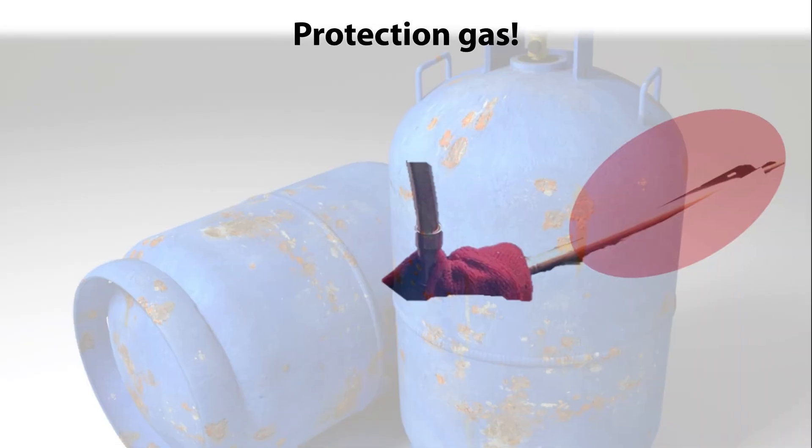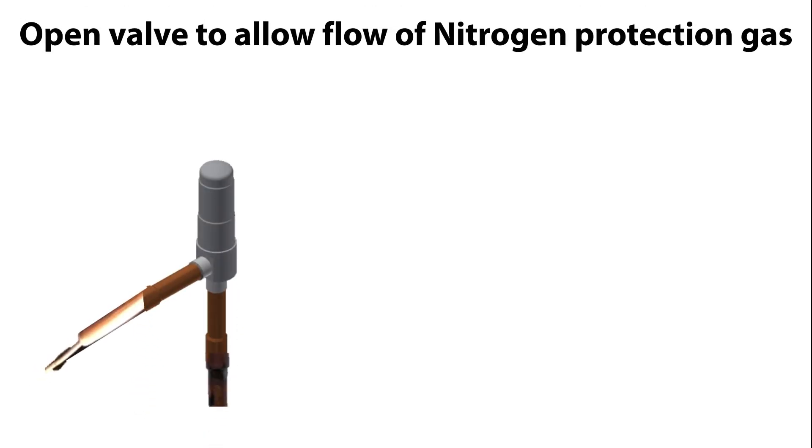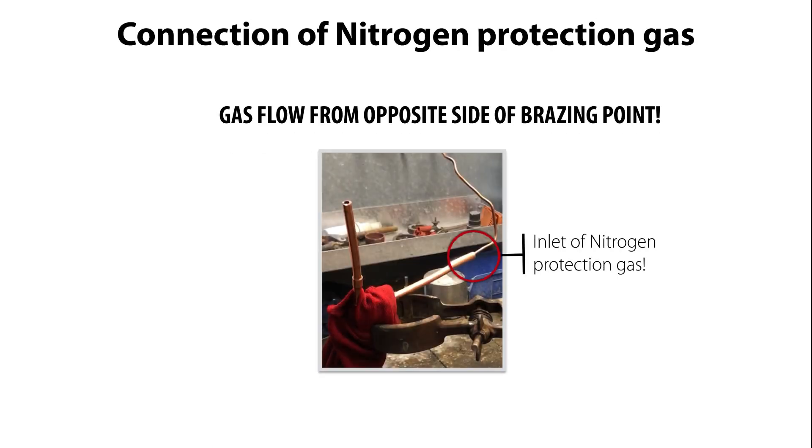The first important step is the protection gas. It is very important to ensure that the valve is fully open to allow flow of protection gas through the valve as seen here. The valve is supplied open but can also be manually opened by using a manual coil as seen here. You need to connect nitrogen protection gas to the valve connection on the opposite side of where you're going to braze the valve to the piping as seen here.